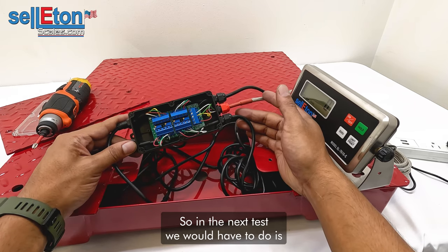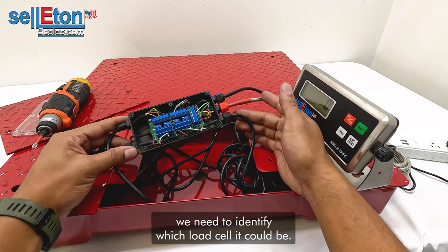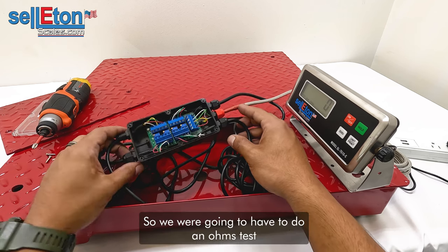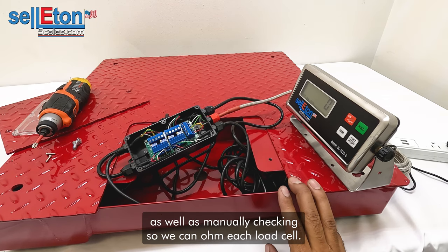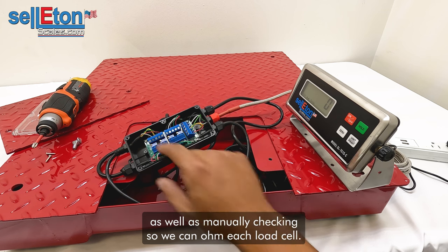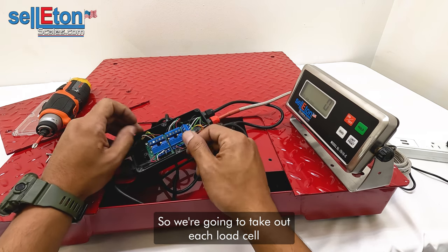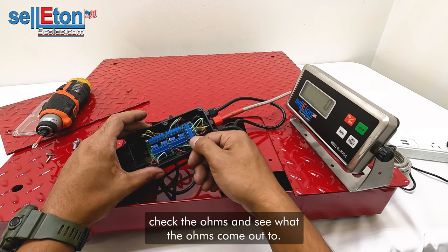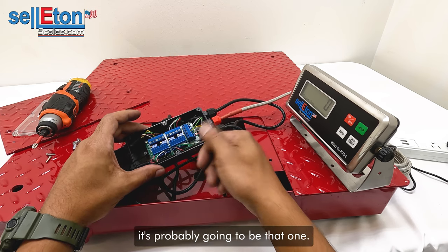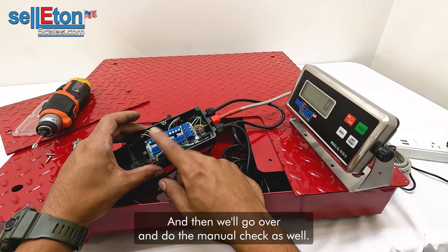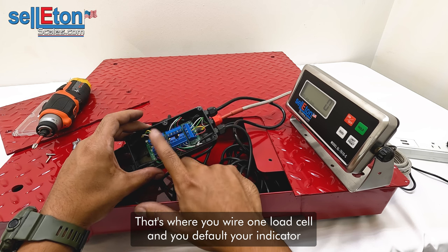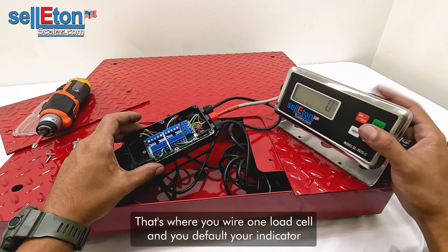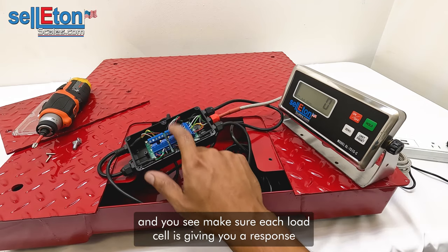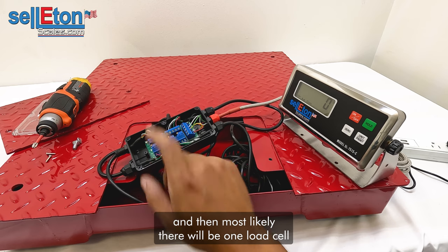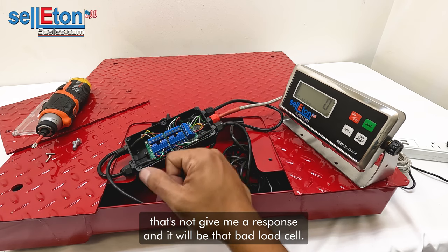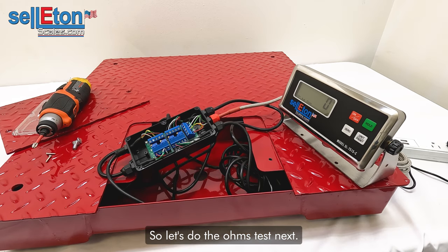So the next test we would have to do is we need to identify which load cell it could be. So we're going to have to do an ohms test as well as manually checking. We can ohm each load cell. We're gonna take out each load cell, check the ohms, and see what the ohms come out to. If we have one that's an oddball out, it's probably gonna be that one. And then we'll do the manual check as well. That's where you wire one load cell and you default your indicator, and you make sure each load cell is giving you a response. And then most likely there will be one load cell that's not giving you a response, and it will be that bad load cell. So let's do the ohms test next.